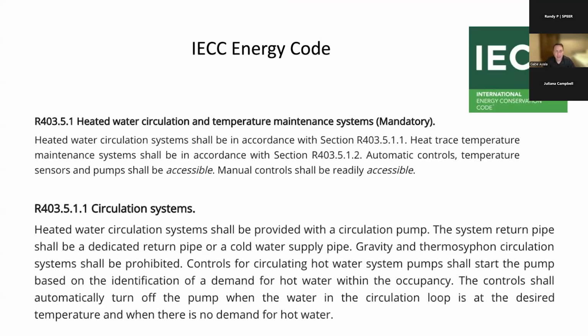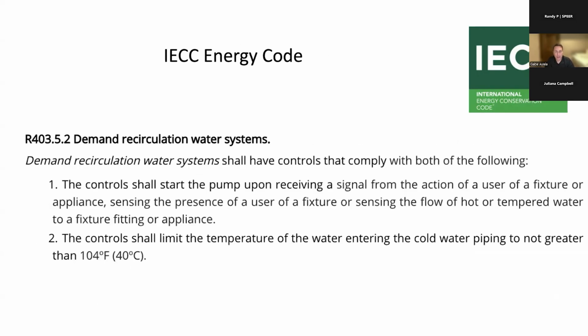IECC has over the years become more and more definitive about what type of controls they want with recirculation. And here we see the residential code section 403.5. What they say here is that controls for recirculating hot water system pumps shall start the pump based on the identification of a demand for hot water within the occupancy, and that the control shall turn the pump off when the recirculation loop is at the desired temperature. And then right after this, they go into more specific detail about what demand recirculation systems mean. It means that the controls shall start the pump upon receiving a signal from the action of a user of a fixture or appliance, sensing the presence of a user of a fixture, or sensing the flow of hot water or tempered water to a fixture or appliance, and that the control shall limit the temperature of the water coming back to no greater than 104.